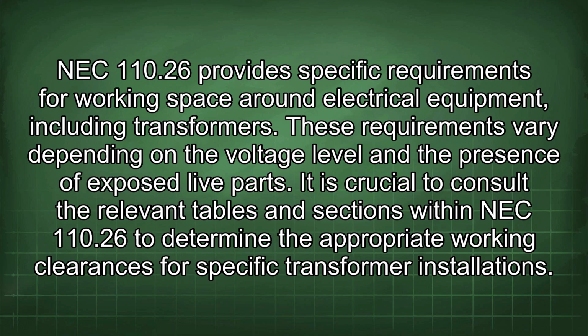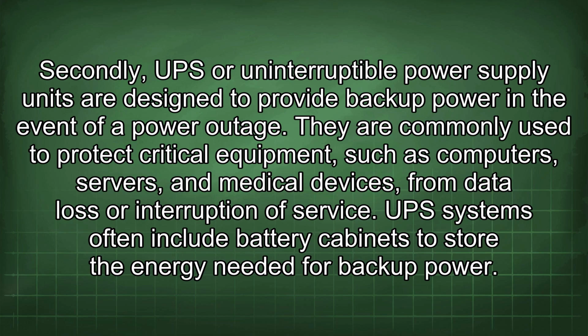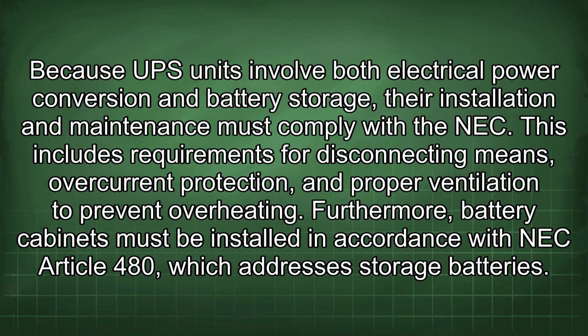specific transformer installations. Secondly, UPS or uninterruptible power supply units are designed to provide backup power in the event of a power outage. They are commonly used to protect critical equipment, such as computers, servers, and medical devices, from data loss or interruption of service. UPS systems often include battery cabinets to store the energy needed for backup power. Because UPS units involve both electrical power conversion and battery storage, their installation and maintenance must comply with the NEC. This includes requirements for disconnecting means, overcurrent protection, and proper ventilation to prevent overheating. Furthermore, battery cabinets must be installed in accordance with NEC Article 480, which addresses storage batteries.